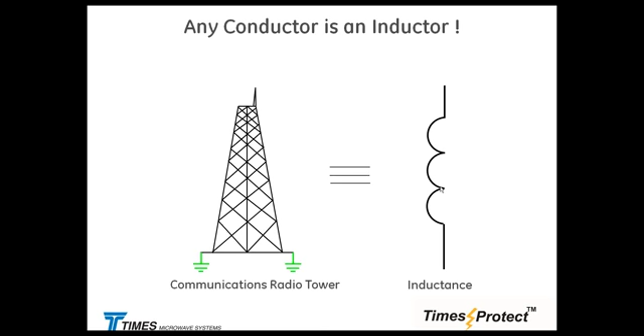There are various ways of calculating inductance. Inductance is treated as an electrical value, but this is purely the geometry of the conductor we are talking about. Typically with a monopole or a three-legged or four-legged tower, we are going to have some mutual inductance working against us. But in the monopole situation, you can assume anywhere from 0.6 to 0.8 microhenry per meter, which is 0.6 to 0.8 every 3 feet or so. And it's going to be linear by nature.